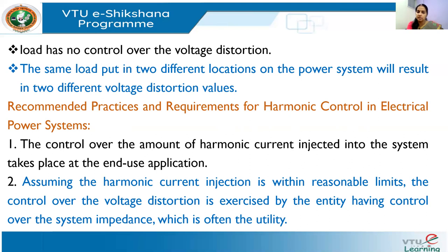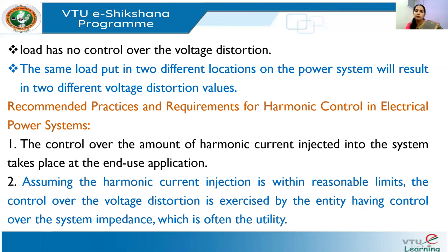By popular convention in the power industry, when the term 'harmonic' is used by itself in reference to load apparatus, it generally refers to current harmonics. When referring to a utility system, voltage harmonics are generally the subject. You should always ask for clarification: current harmonic (load side) or voltage harmonic (utility side). Generally, current distortion refers to the load side, and voltage distortion refers to the utility side.